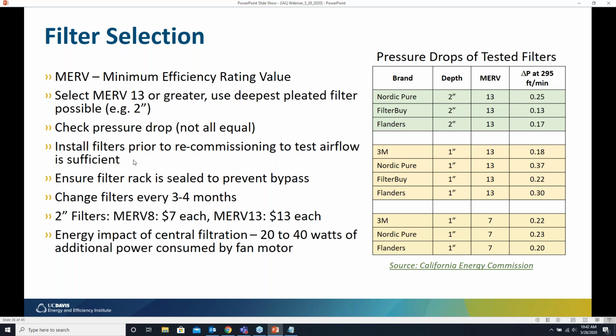Install your filters prior to recommissioning and testing your airflow. That way, when you do that recommissioning, you'll be able to confirm that your airflow is sufficient. Ensure your filter rack is sealed to prevent bypass, and change your filters every 3 to 4 months. The longer, the more like the 4 months, I would consider if you have the 2-inch deep filters.